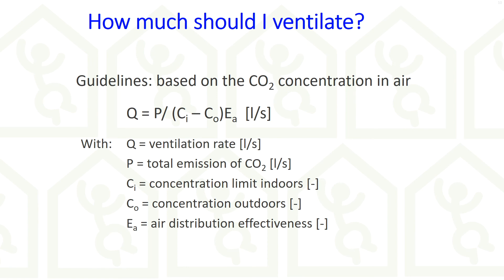How much ventilation is required? This is not an easy question to answer. Current guidelines for indoor air quality are mainly based on the CO2 concentration in air that is allowed. CO2 is used as an indicator of the presence of people. With the equation shown here, it is possible to calculate the required ventilation rate per person in a space to keep below the allowed CO2 concentration. The air distribution effectiveness in that equation tells us something about how effectively the air is distributed — for complete mixing, this value is 1.